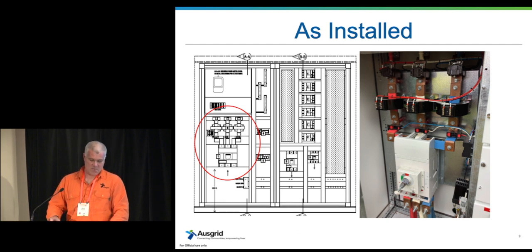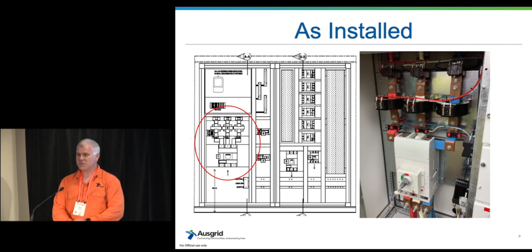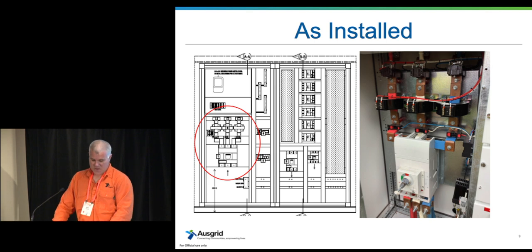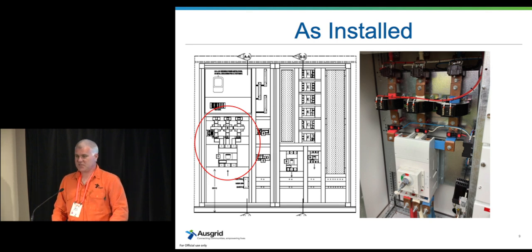From memory, there were about 12 odd defects within that photo that we looked at, and quite a few of them are not going to allow energisation. This was on a weekend job. It was on a Saturday, so the switchboard builder's not available because they're not working on the weekends, they mustn't be that busy. But we've now got significant issues here where supply's not going to be able to be energised because they're going to have to make some significant modifications to that switchboard.